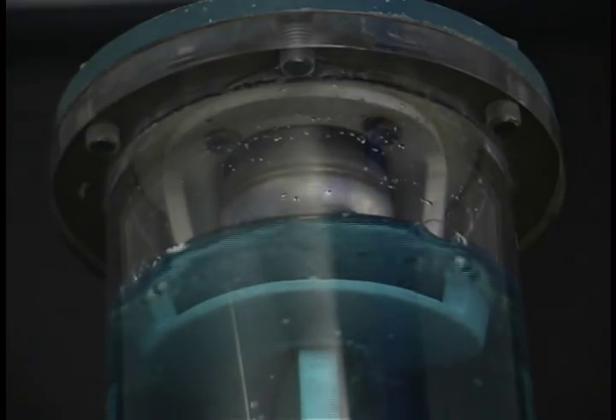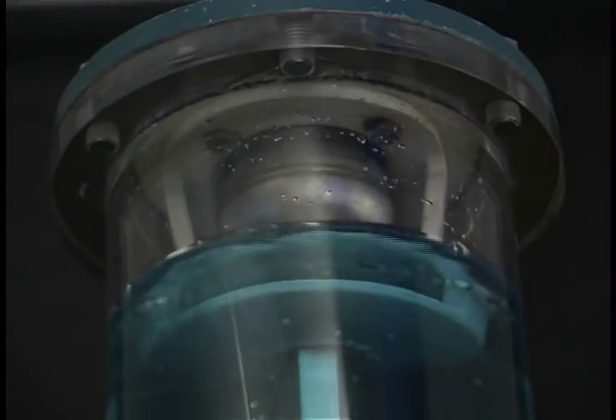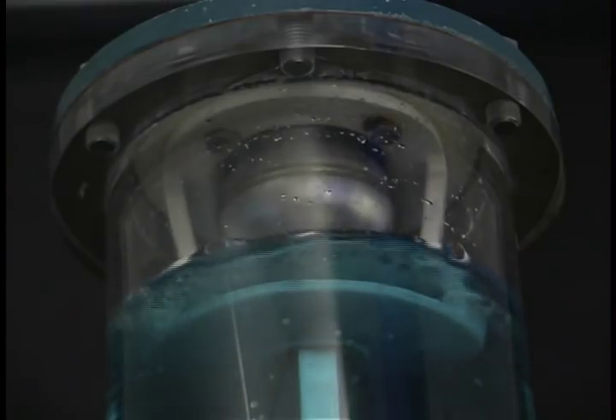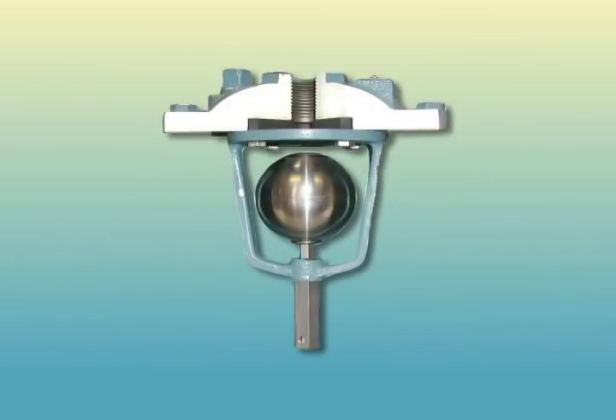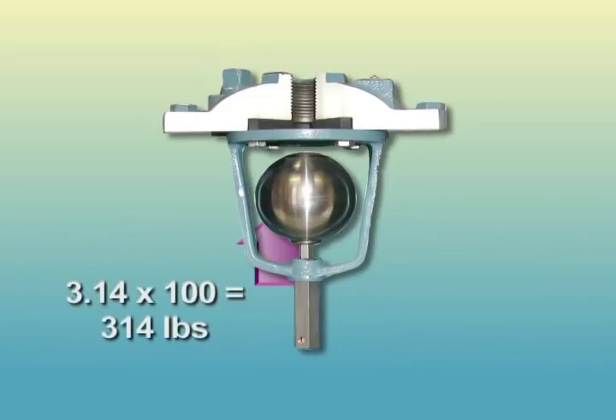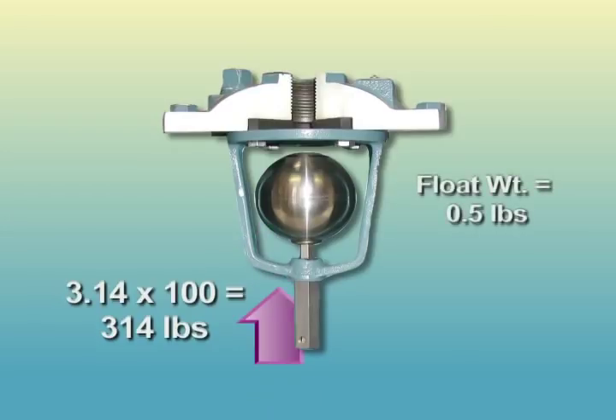Note that as the water recedes, the float stays in the closed position. The float remains in position due to the forces holding it against the seat. This is because forces acting to keep the valve closed are greater than the forces acting to open it. The force is determined by calculating the outlet area times system pressure, which in this case equals 314 pounds of force. The only force acting to open the valve is the weight of the float, which here is one half pound. As a result, the valve will not open under system pressure.